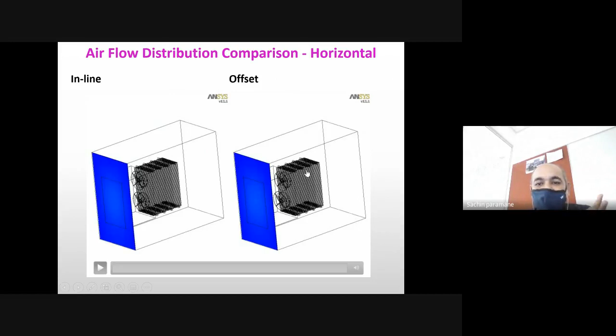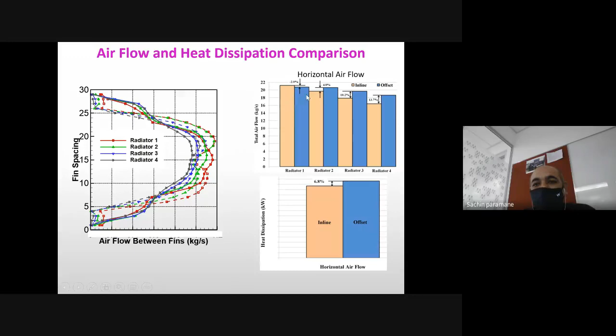So you can see that there is a decrease in the heat dissipation as we move away from the first radiator. This decrease in the airflow is 2%, 5%, 10%, and 14%. That means the first radiator will get the maximum amount of air and hence it has higher heat dissipation. But as we move away from the fan, there is a gradual decrease. Now this is for inline, and for offset the same trend is observed, but the decrease in heat dissipation is lower compared to the inline. Now, for this type of fan in the horizontal airflow, there is around 7% improvement in the heat dissipation. Sorry, with the fans offset.